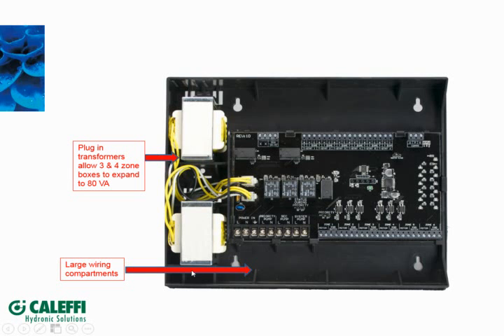All right. Well, this is the zone valve box with the cover removed, after you've installed the two transformers. Like I mentioned, the 3 and the 4 zone come with a single 40 VA, but they are expandable to 80 real quickly and simply. The 6 zone comes with 2 transformers in the box.